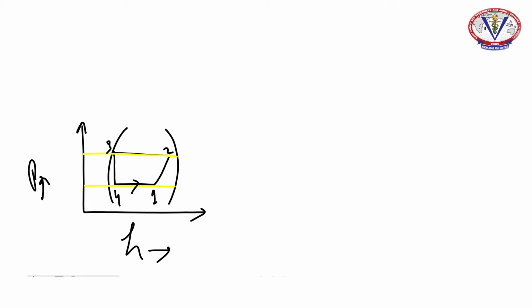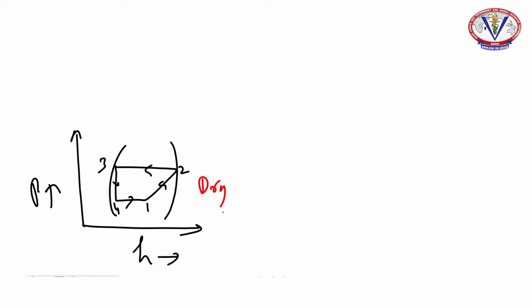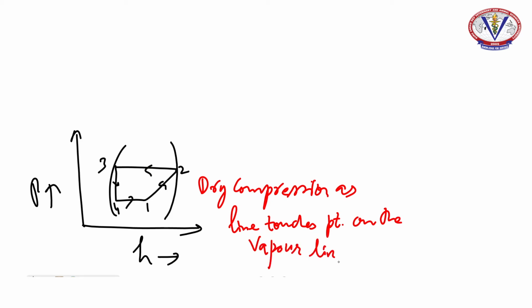The various possible refrigeration cycles can be shown on the pH plot. As we can see in this diagram, the compression process and the evaporation process, that is point 1 and point 2, lie between the liquid line and the vapor line. Therefore, such a process is called wet compression process. Similarly, we can see on another diagram that point 1, the end of evaporation, is still between the liquid and vapor line, but at the end of compression point 2 lies on the vapor line. Therefore, this process is called dry compression process.